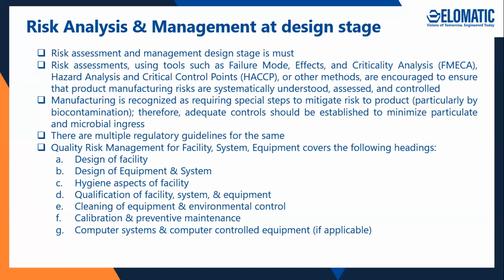I have also covered a slide where risk analysis or quality risk assessment has been done at the production shop floor stage. So when designing a new facility, systems, or equipment, we need to take care of the design of the facility, whether it has already undergone a risk assessment, whether contamination can prove fatal to the people working there, and whether containment has been done appropriately and that risk has already been evaluated.